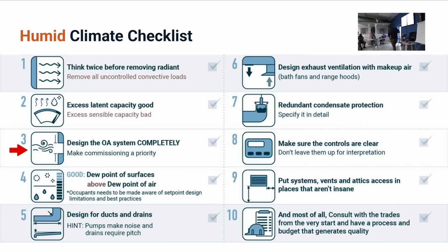Design the outdoor air system completely. If you're going to do an outdoor air system, design it—how much air do you want to bring in, how often, what are the controls and all that. You cannot just send a technician out and say, hey, outdoor air vent, bring in some outdoor air. No—think it through, design it.